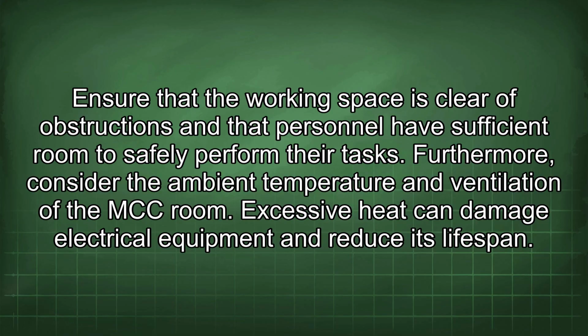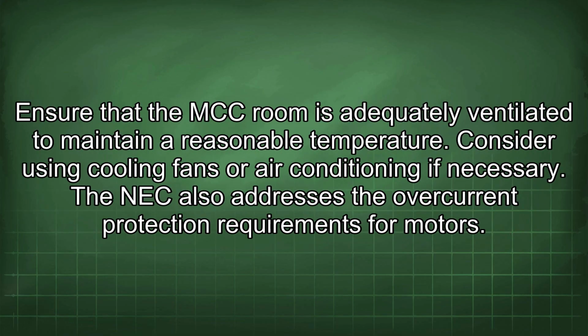Furthermore, consider the ambient temperature and ventilation of the MCC room. Excessive heat can damage electrical equipment and reduce its lifespan. Ensure that the MCC room is adequately ventilated to maintain a reasonable temperature. Consider using cooling fans or air conditioning if necessary.